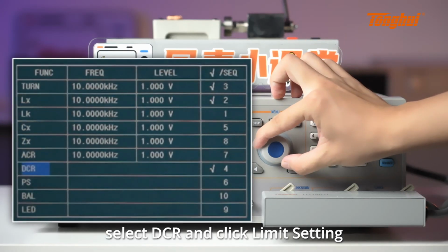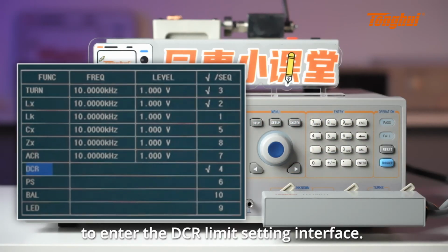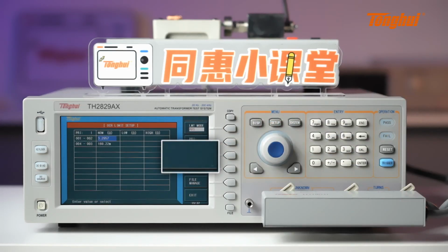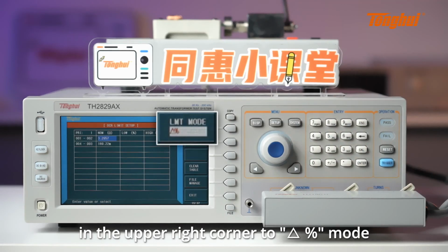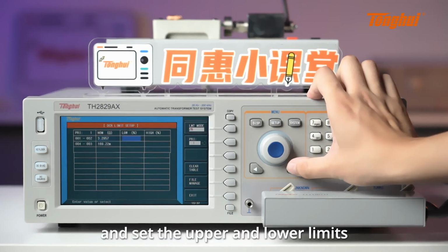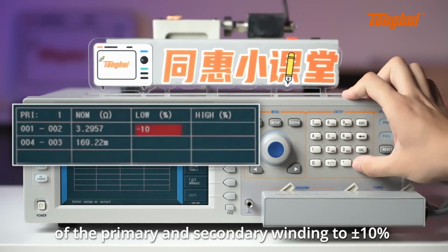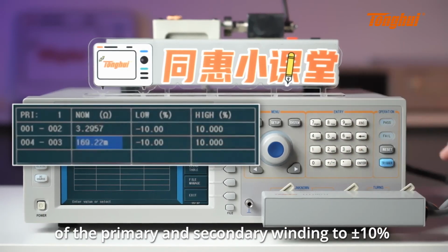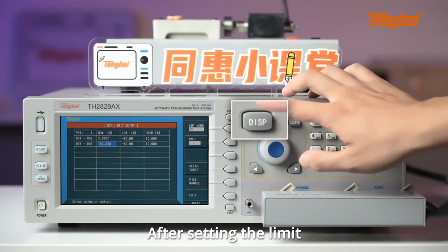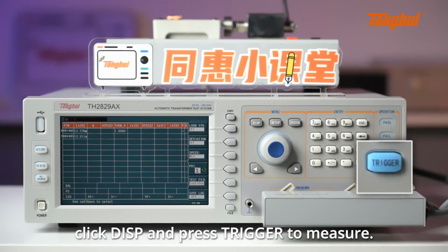Select DCR and click Limit Setting to enter the DCR limit setting interface. Change the limit mode in the upper right corner to percentage mode and set the upper and lower limits of the primary and secondary windings to 10%. After setting the limit, click Display and press Trigger to measure.